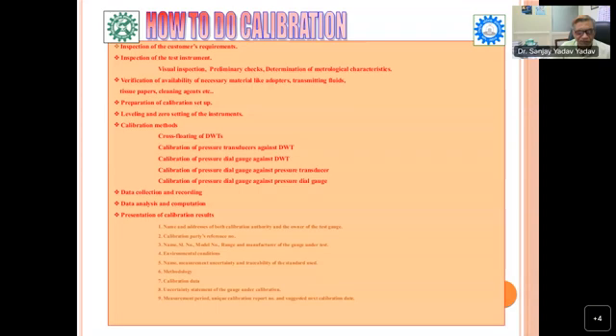Inspection of the test instrument: it can be visual inspection, it can be a preliminary check, determination of metrological characteristics, then verification of availability of necessary material. To calibrate this equipment you need the adapter, transmitting fluid, cleaning agent, tissue paper. You must have all these. Then preparation of calibration setup.